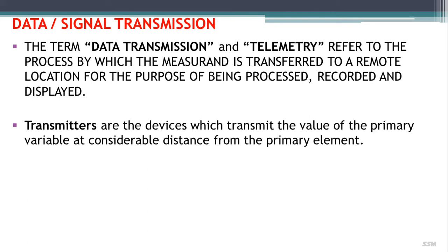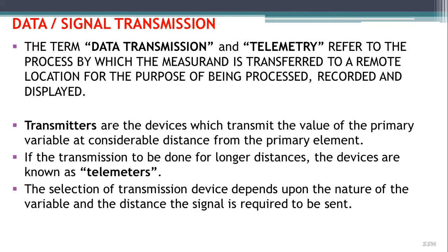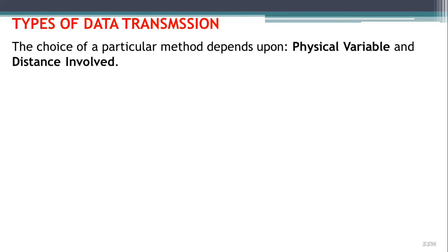Transmitters are devices which transmit the value of the primary variable at a considerable distance from the primary element. If transmission is to be carried out over a longer distance, those devices are known as telemeters. The selection of transmission devices depends upon the nature of the variable and the distance the signal is required to be sent. For transmission, the measured variable is converted to a transmittable signal, either pneumatic or electric, so it can be recovered by a remote indicating, recording, or controlling device.